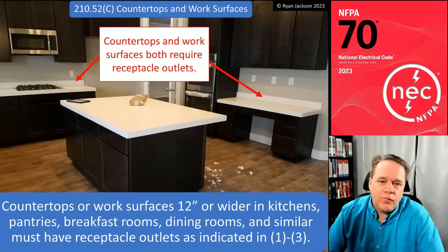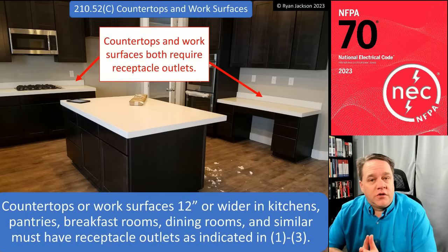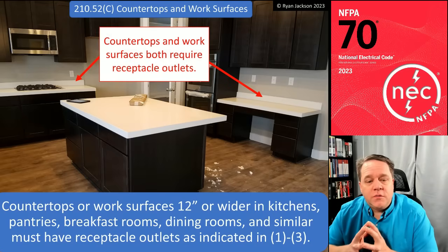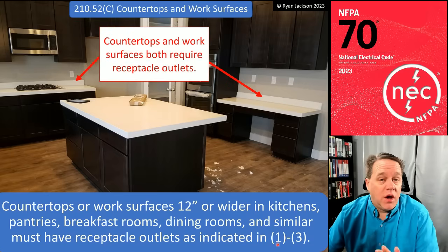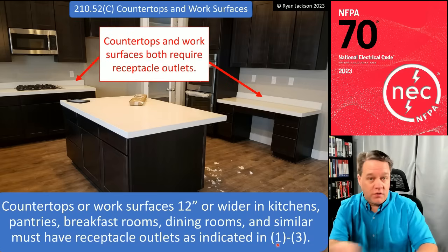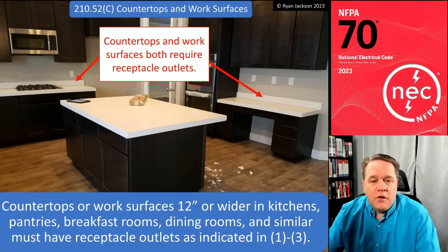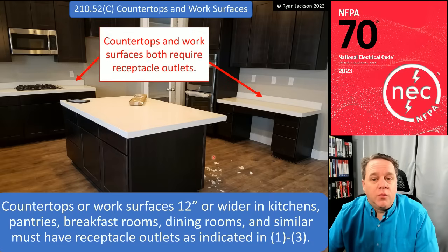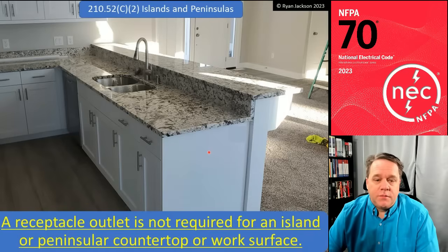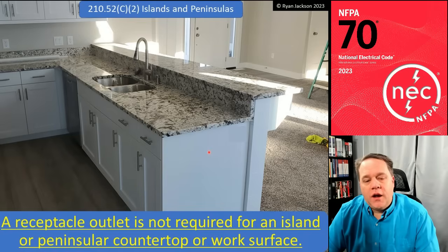Let's go to subsection C — I'm only going to talk about islands and peninsulas here. Countertops or work surfaces that are 12 inches or wider in kitchens, pantries, breakfast rooms, dining rooms, and similar areas must have receptacle outlets as indicated in items one through three. Item one covers wall-space countertop receptacles and didn't experience significant changes, so we're not going to cover that.